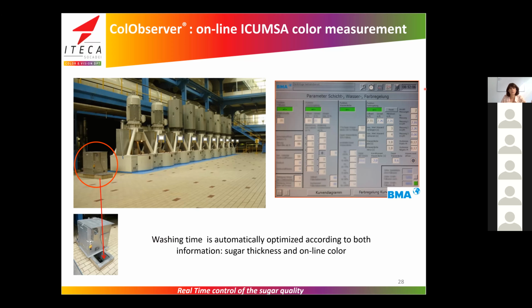In this case, the PLC of the centrifugal uses two types of information to optimize the washing time: the sugar color delivered by the ColObserver, and the basket sugar thickness given by the radar sensor. The centrifugal PLC displays the last three color measurements of a centrifugal. The washing time is set according to the sliding average over these three measurements and the thickness measurement. The washing time remains active on color even when the thickness radar measurement is off.